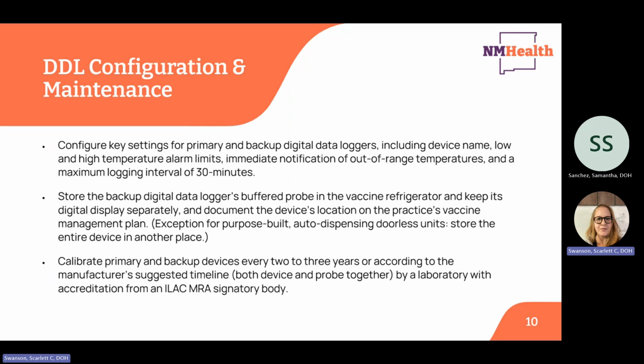Calibrate your primary and backup devices every 2 to 3 years or according to the manufacturer's suggested timeline. Always send the device and the probe together unless the manufacturer says otherwise, of course. So if the manufacturer supplies a pre-calibrated replacement probe upon device calibration expiration, the device and probe don't need to be calibrated together.